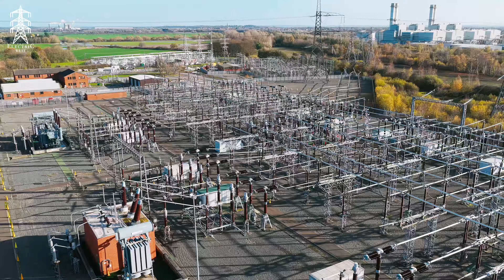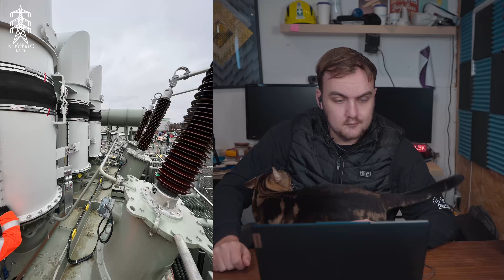For this video, the idea of having a bus duct is that you take that normal air insulated bus bar, AIB, but you put a duct around it to protect it, and that gives you more control of the insulation around it. So with a normal air insulated bus bar, if you've got 2 bars running parallel, if something was to fall between them, for example a bird flies between them, or in distribution sometimes a small animal might bridge across the 2 because the gap is that small, that bridging will cause a short, and that will cause a blackout or a fire or damage to equipment. So what you can do is put this duct around it, which is a mechanical protection, and that gives you more control to make sure you're not having a phase to phase arc short circuit essentially.